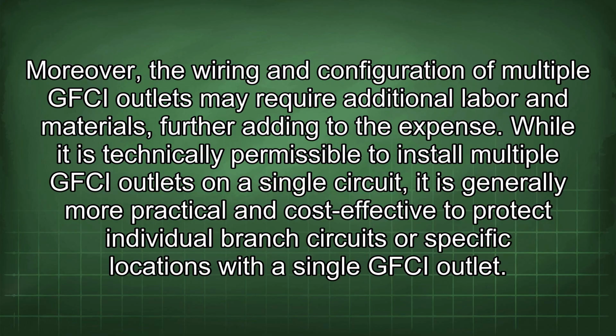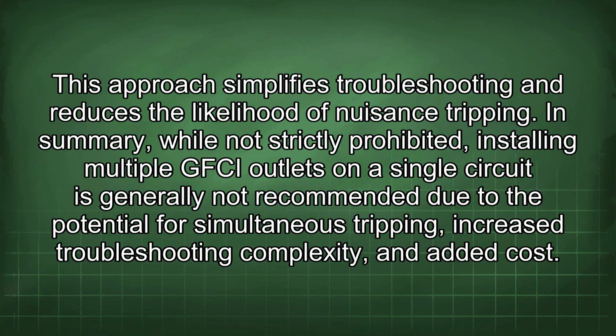While it is technically permissible to install multiple GFCI outlets on a single circuit, it is generally more practical and cost-effective to protect individual branch circuits or specific locations with a single GFCI outlet. This approach simplifies troubleshooting and reduces the likelihood of nuisance tripping.